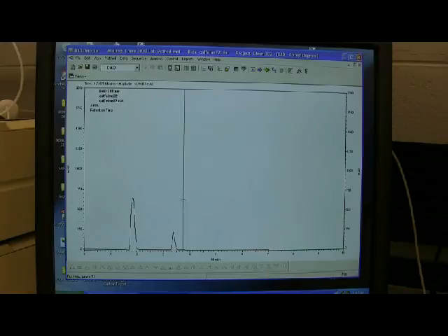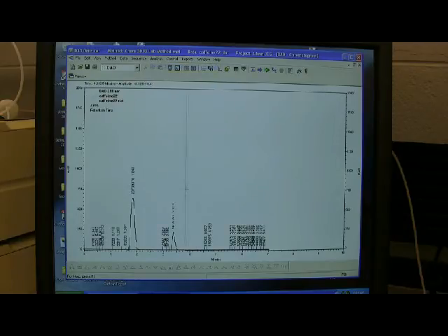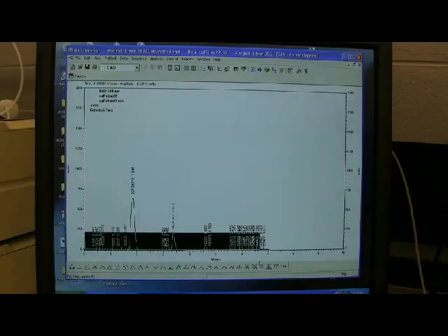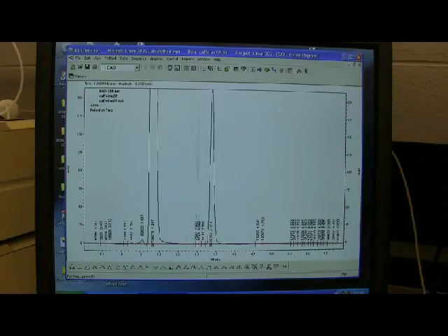So next we want to do is analyze them. Go to analyze, analysis, and then analyze. This gives you your area and your retention time. We want to get rid of all this stuff. If you look, there's usually a small peak somewhere near your first peak. You can see here, we want to set the baseline to the top of this peak.